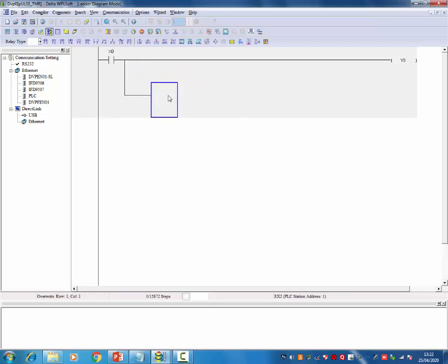So for the pulse delay timer, if we turn on the switch, the output will be in on condition, and after some time delay, the output will go to off condition, but still the switch is in on position only. So I'm triggering my output with an input once, and after a certain time delay, the output will be off. I'm going to show you how it works.